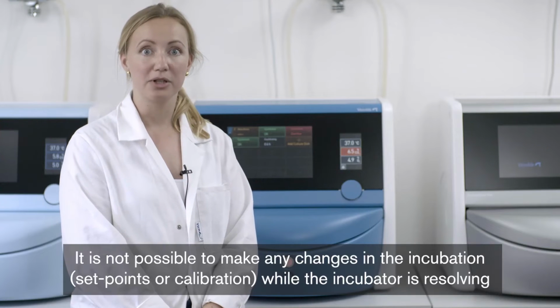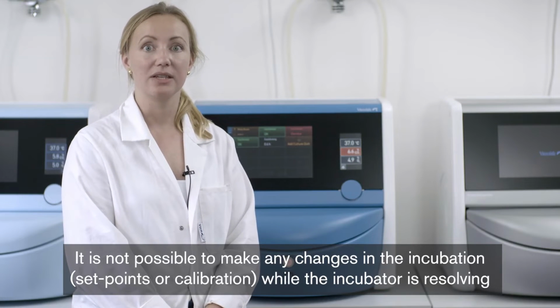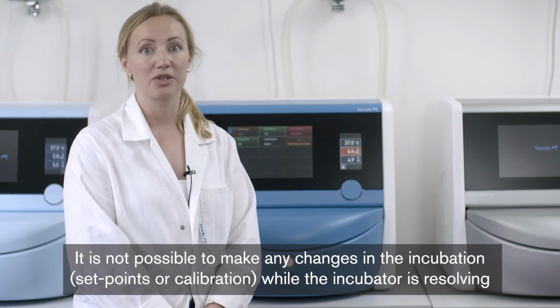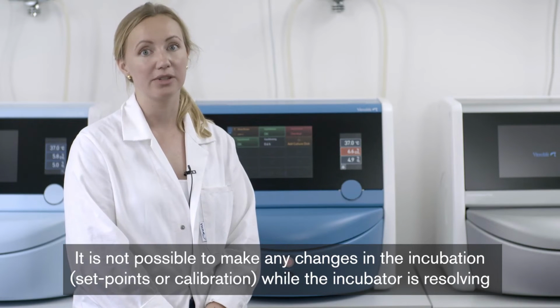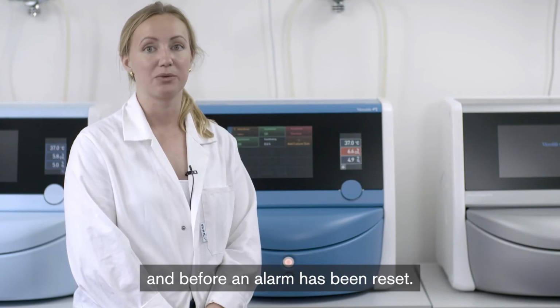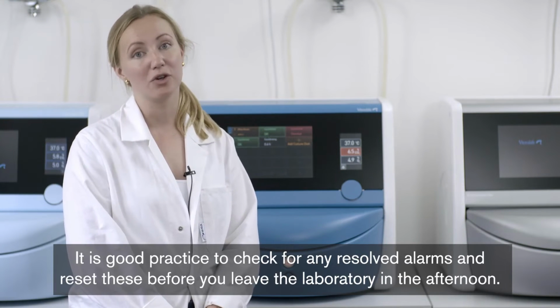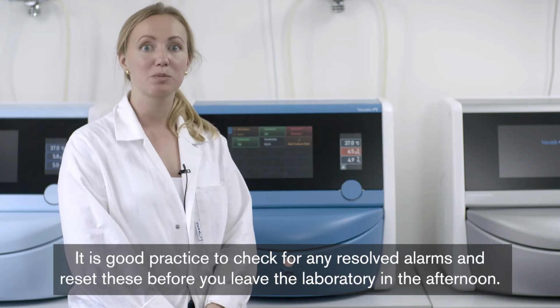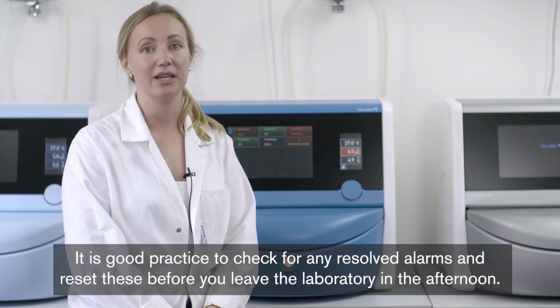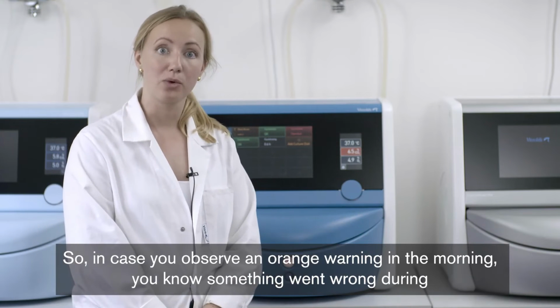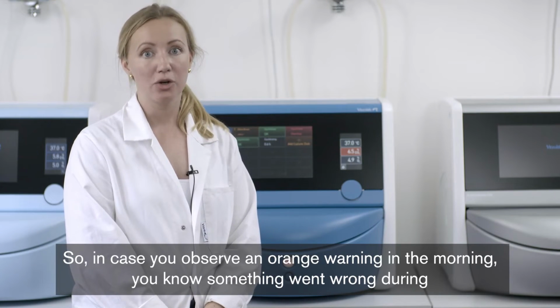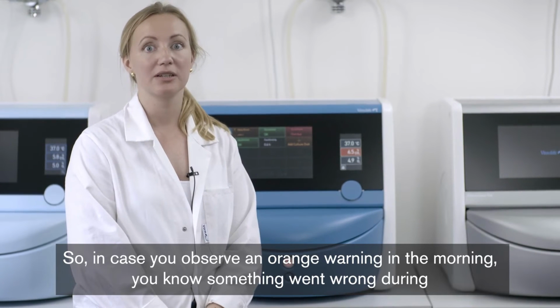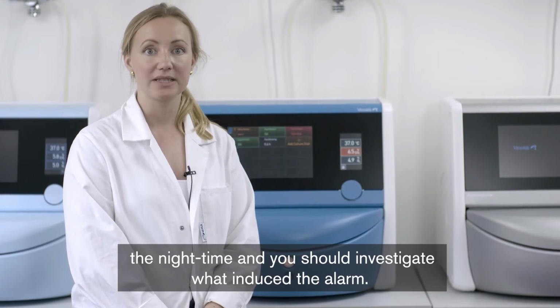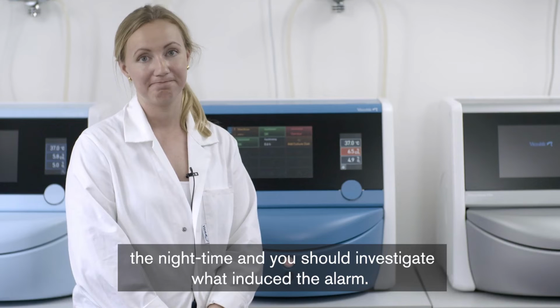It is not possible to make any changes in the incubation, set point or calibration while the incubator is resolving before an alarm has been reset. It is good practice to check for any resolved alarms and reset these before you leave the laboratory in the afternoon. So, in case you observe an orange warning in the morning, you know something went wrong during the nighttime and you should investigate what induced the alarm.